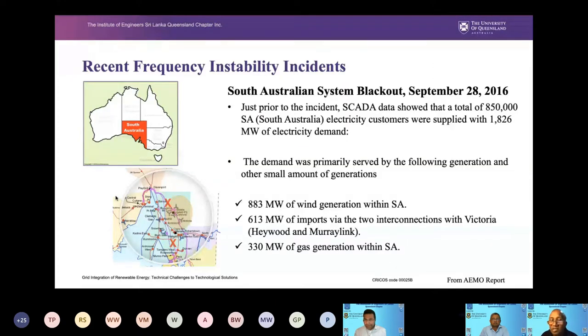If you look at the whole eastern grid, it may be about 23,000 megawatts of peak demand. But I'm talking here only about South Australia. At the point just before that blackout, we had 1,826 megawatts of demand. And this demand was supplied by wind. A substantial share was supplied by wind energy, closer to 50%.